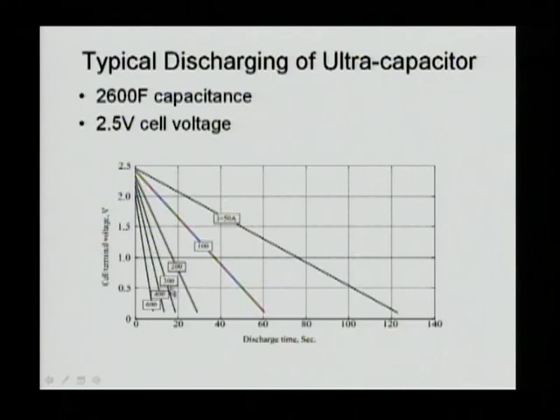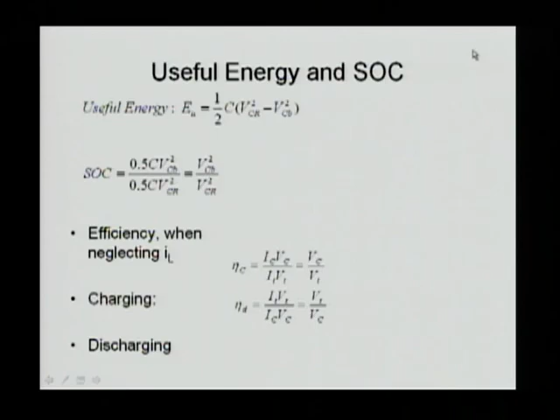Useful energy in an Ultracap is also very large. You can discharge it almost down to zero, though if the voltage is too low you may not be able to use it. But ideally, discharging the voltage down to 0 volts does not damage the life of the Ultracap, so you can basically run millions of cycles without problem. The lifetime of an Ultracap is definitely not an issue when you use them. The only issue at this moment is energy density and the large size.